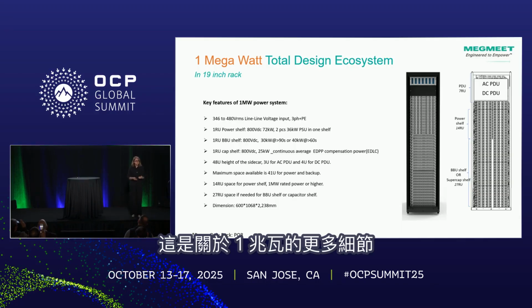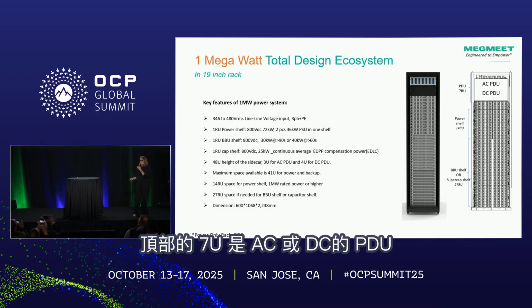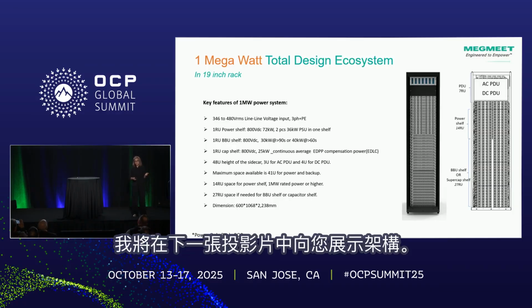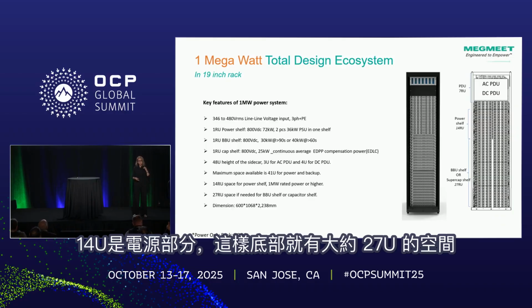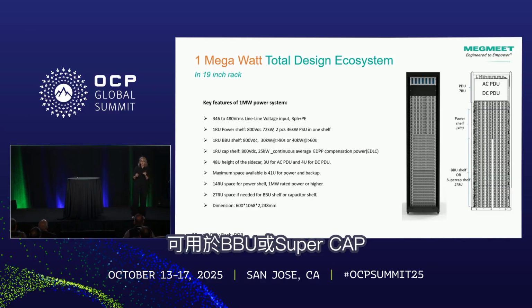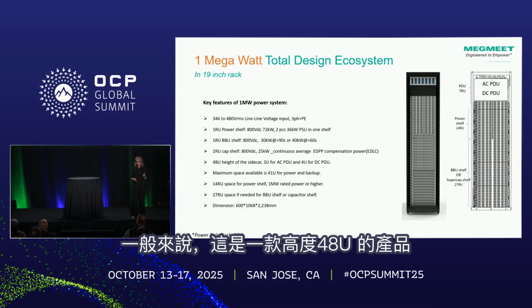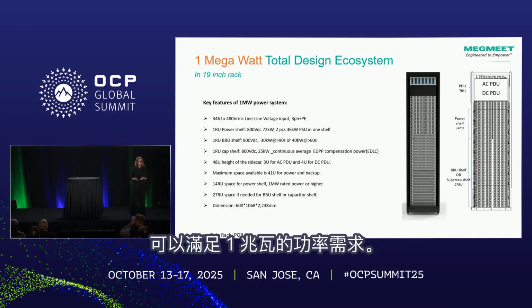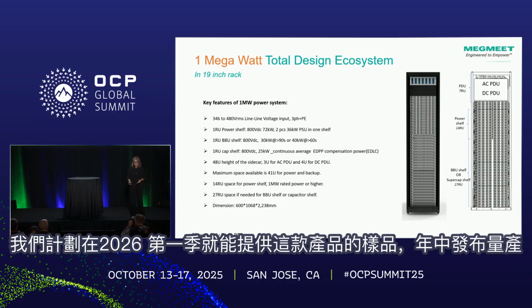So this is more details on the 1 megawatt. 7U on top is the PDU, AC or DC. Basically, I will show you the architecture in the next slide. 14U is the power, and that allows about 27U in the bottom for either battery backup or power capacitor shelf. In general, this is a 48U, and that gets you to complete 1 megawatt power. We have plans to release this part in mid-2026, and we have samples in Q1.